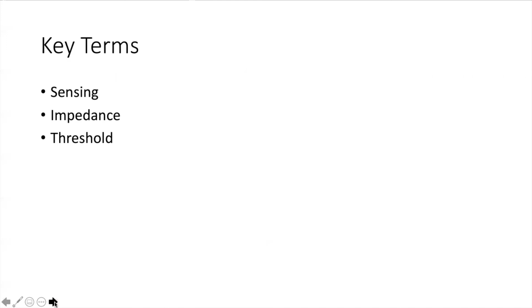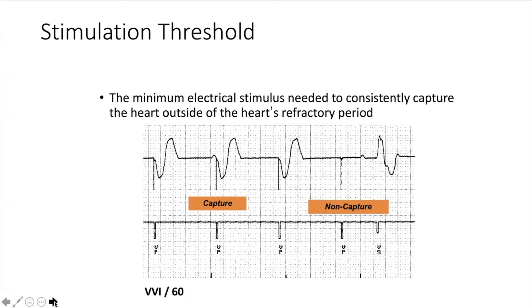All right. It's also important to know some key terms about pacemakers before we get going into how to interrogate someone. And these key terms are sensing, impedance, and threshold. So threshold, or stimulation threshold, is the minimum electrical stimulus needed to consistently capture the heart outside of the heart's refractory period, meaning how much voltage you need to administer in order to capture the myocardium. And this is generally expressed in voltage plus pulse width, so how long the stimulus is delivered. And here you can see on the left, you have a pacing stimulus with capture. And on the right, you have a pacing stimulus, but no depolarization, so non-capture.